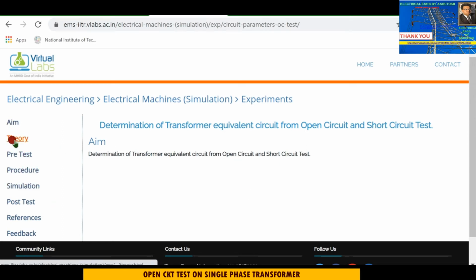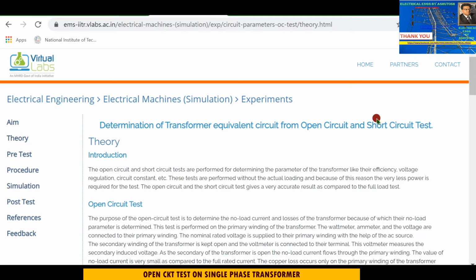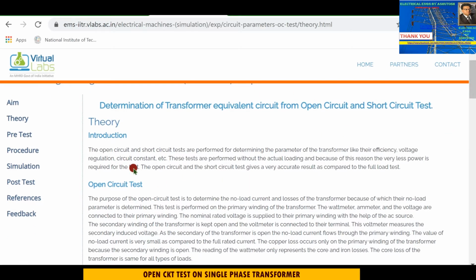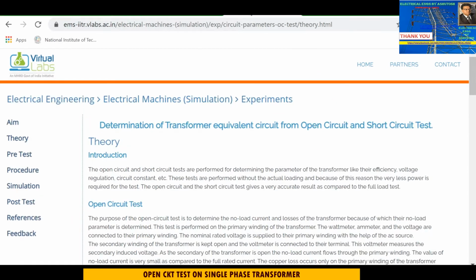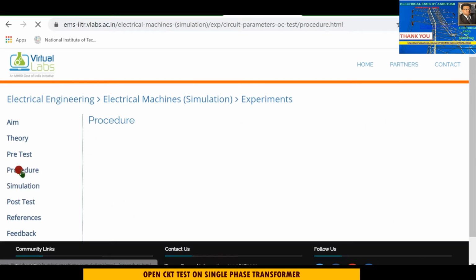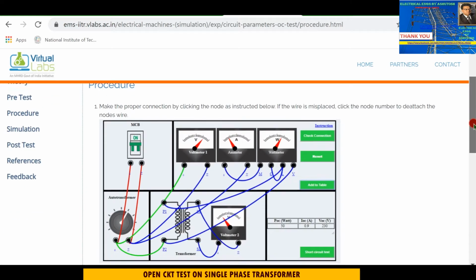You can select theory. Why the open circuit test and short circuit test are conducted, you can read here. The open circuit test and short circuit tests are performed for determining the parameters of the transformer, like efficiency, voltage regulation, circuit constants, etc., and also losses. These tests are performed without actual loading. Because of this, very little power is required for the test.